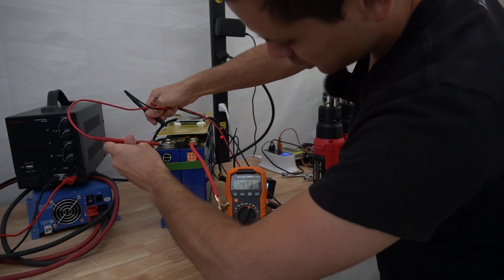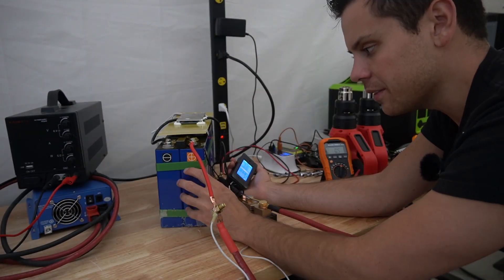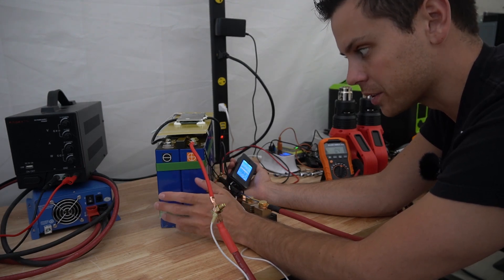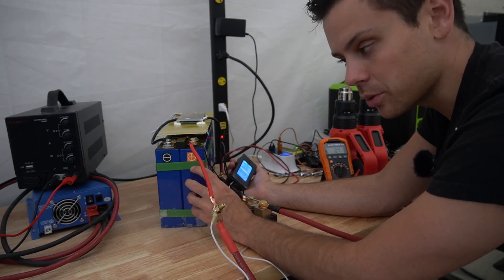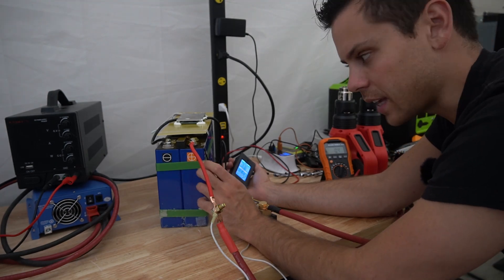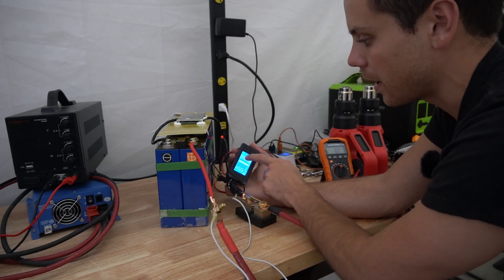2.6, 2.5, 2.4, 2.4. So that's okay. Now something to keep in mind is even though this is rated for 95 amp hours and we pulled 97 amp hours, these were tested individually to pull 98 amp hours. So either one cell is actually 97 amp hours or they need to be balanced to get that remaining one amp hour.